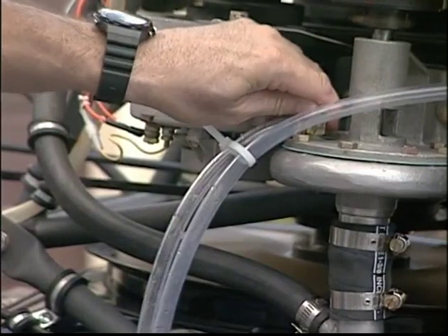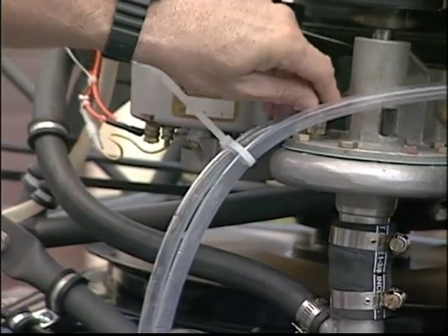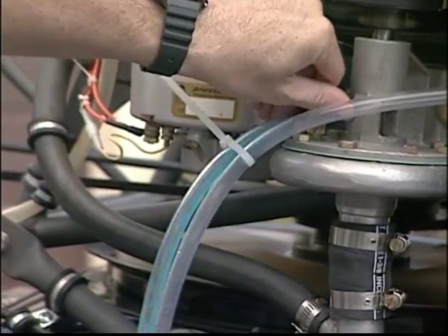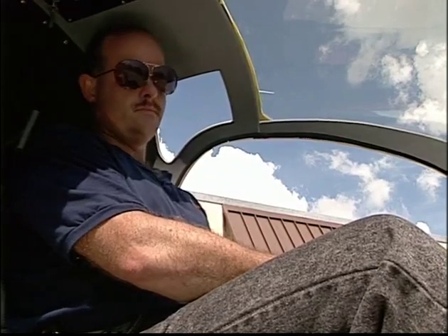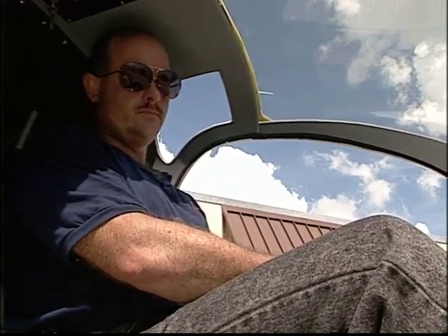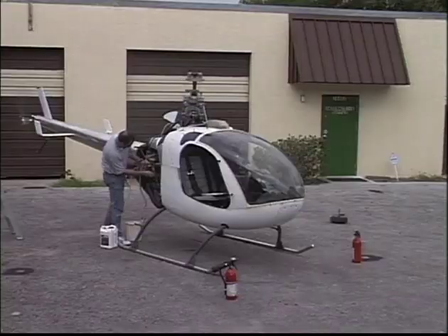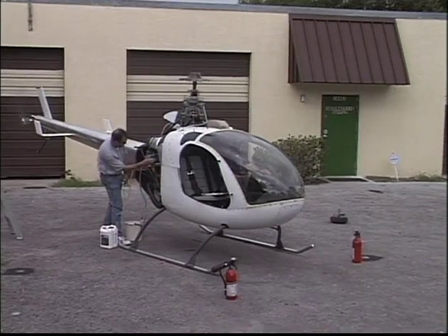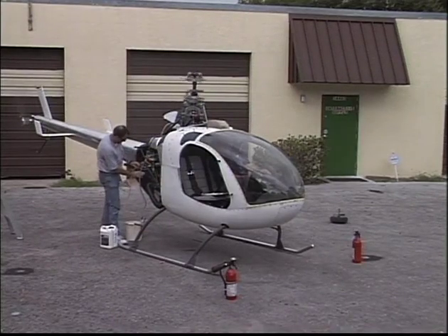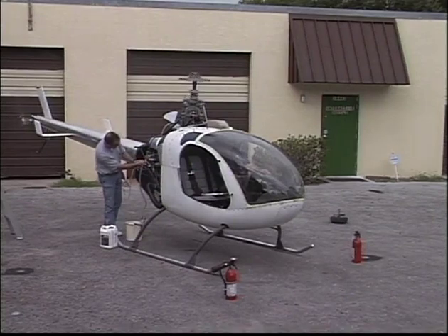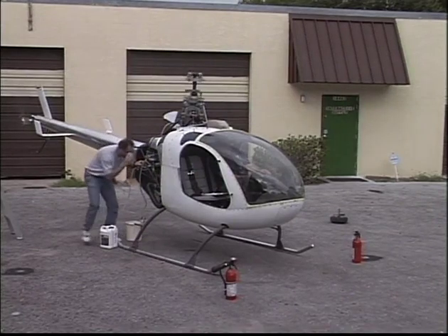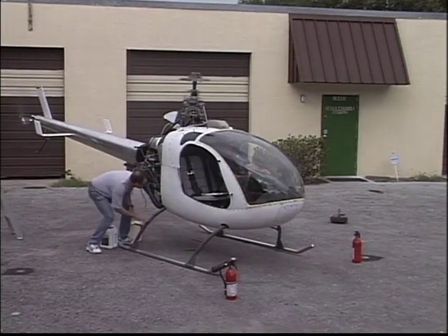Water pump priming and air removal is one aspect of the initial engine startup which requires two people. One person, the pilot, must start the engine and monitor all instruments. The other person is needed to bleed air from the system and to check the cooling system for leaks. This person will also be in an excellent position to watch for several other systems for potential problems.